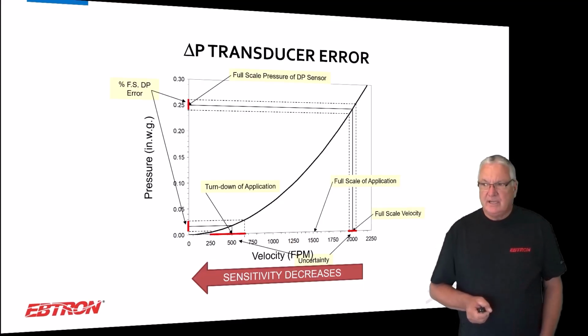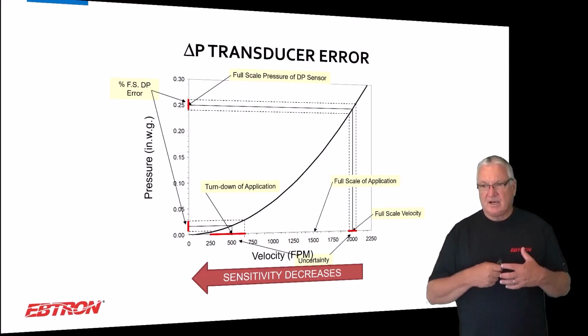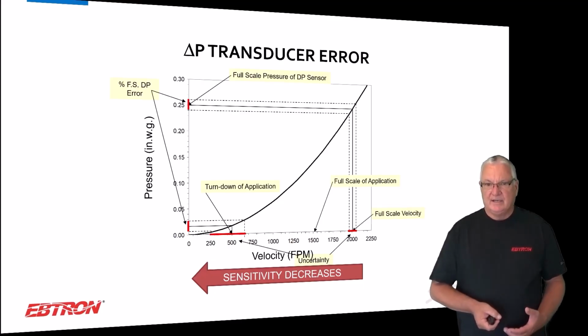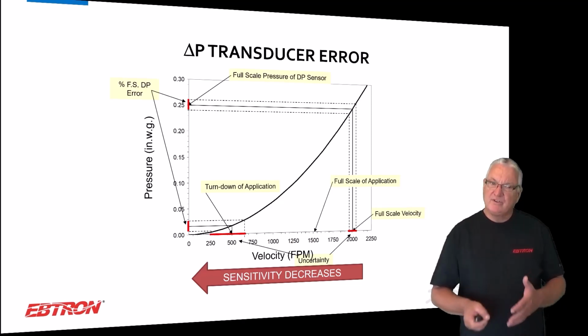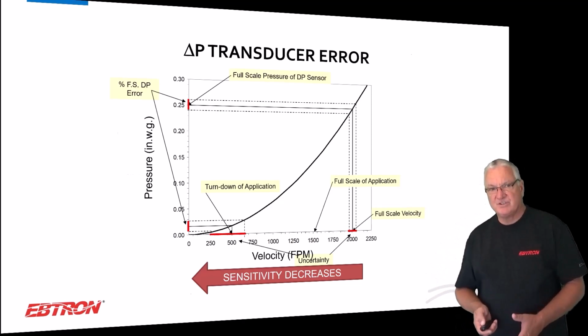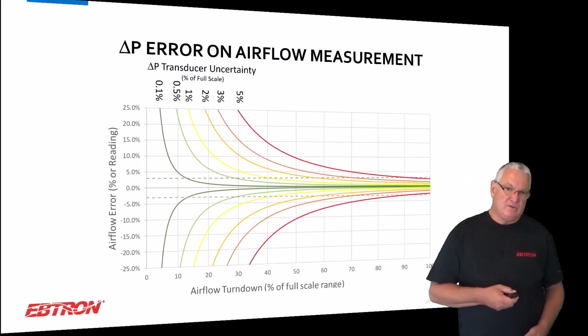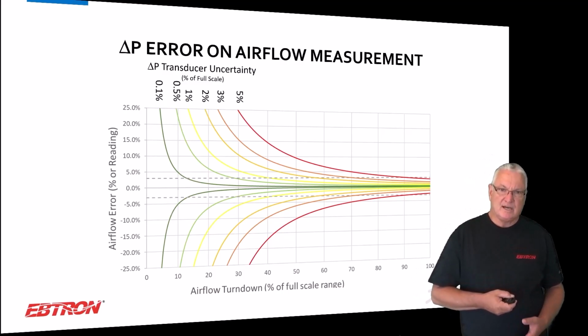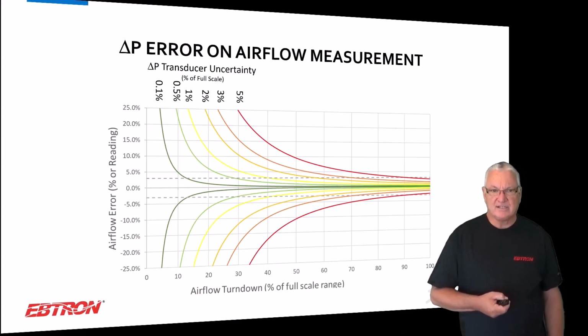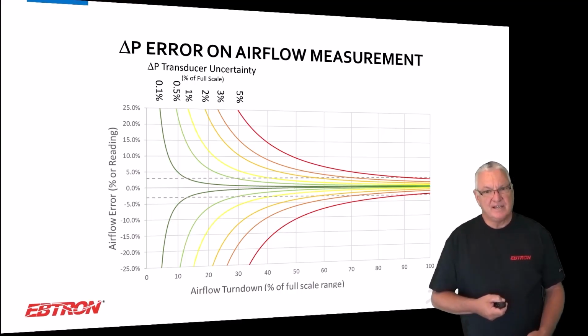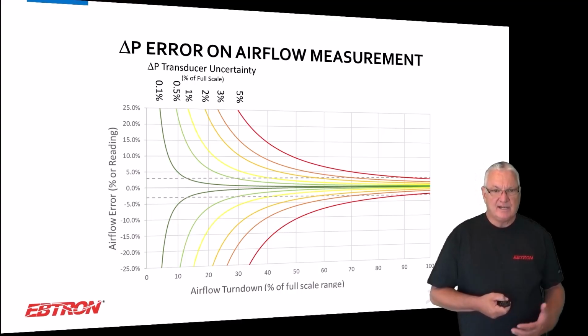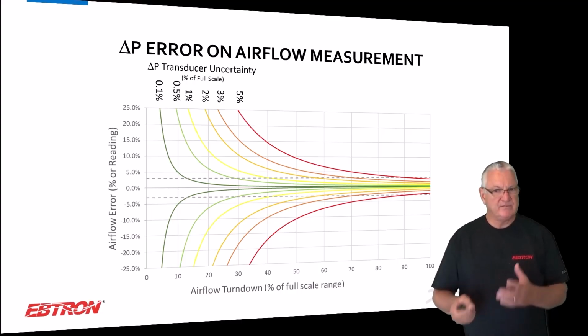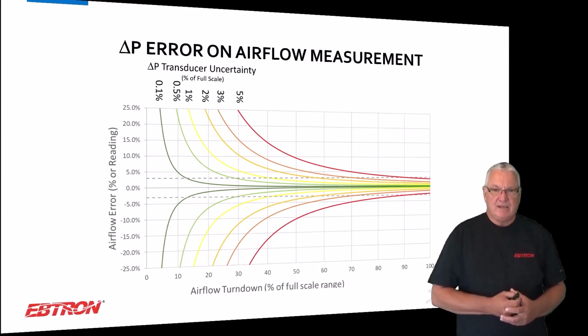And it really matters on the selection of the pressure sensor. Some of these pressure sensors are marginal in performance for using them for flow measurement. They may be fine for using them for pressure measurement. So what you want to do, and this is just me putting it together for you, is look at different % of full scale accuracies, and I'm putting 0.1% to 5%, and looking at the airflow error as a % of reading based on the turn down of the full scale of the device. So 100 is the full scale of the device, and you might be running at 50% of the full scale of the device.